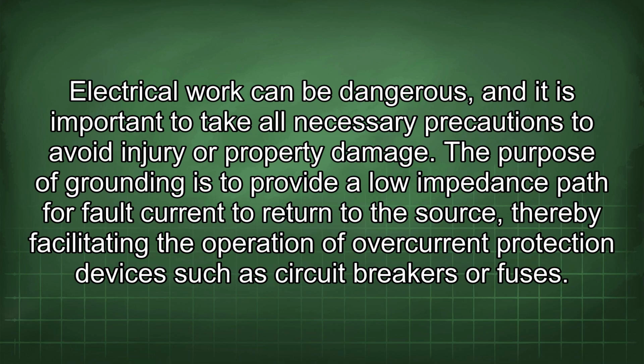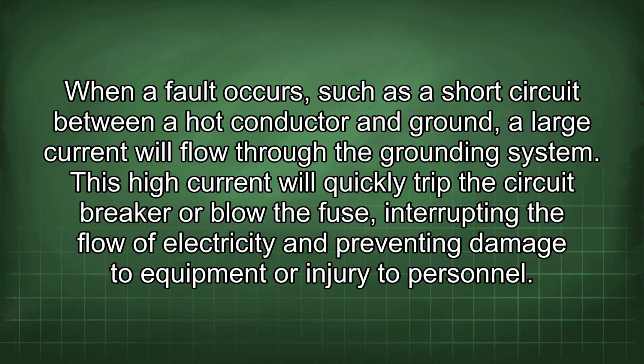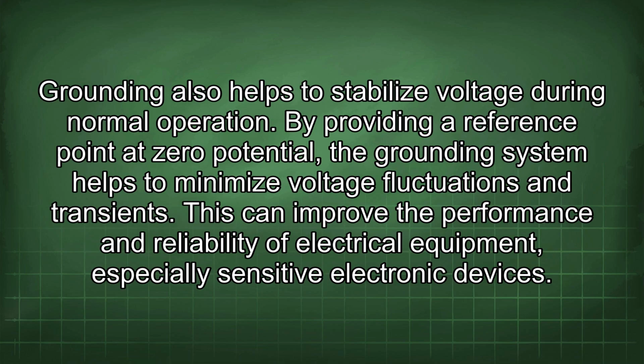The purpose of grounding is to provide a low impedance path for fault current to return to the source, thereby facilitating the operation of overcurrent protection devices such as circuit breakers or fuses. When a fault occurs, such as a short circuit between a hot conductor and ground, a large current will flow through the grounding system. This high current will quickly trip the circuit breaker or blow the fuse, interrupting the flow of electricity and preventing damage to equipment or injury to personnel. Grounding also helps to stabilize voltage during normal operation. By providing a reference point at zero potential, the grounding system helps to minimize voltage fluctuations and transients.